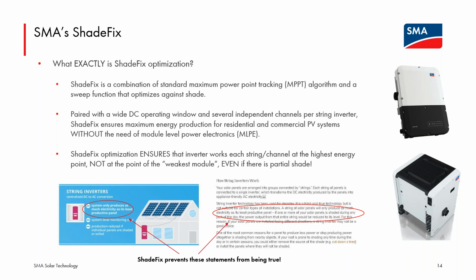And I don't want to spend too much time on what it is. You may have seen on industry websites, this screen capture I took is probably 3 years old now, but certainly I think misleading at the time, and you may see statements like this, that a string inverter is capable of only working at the point of the weakest module in the string. And the whole point of ShadeFix is to prevent that statement from being true. It is an optimization algorithm that is based in the inverter that prevents the inverter from being stuck at that quote unquote point of the weakest module should there be partial shade on the array. And again, each of the 6 tracking channels for the CORE1 is going to have this ShadeFix optimization testing the best point.